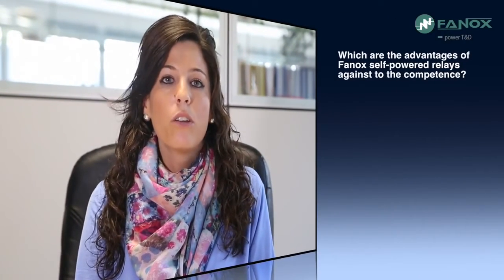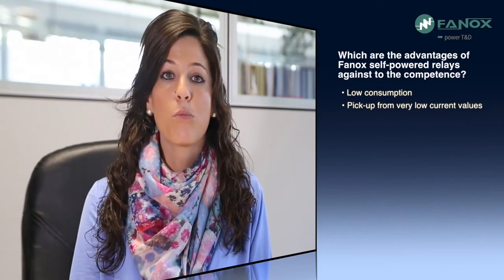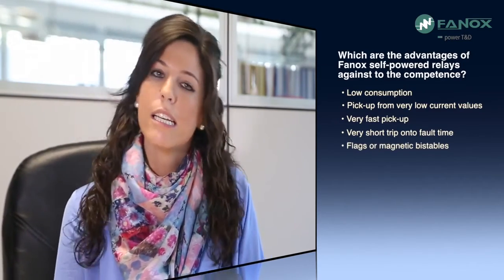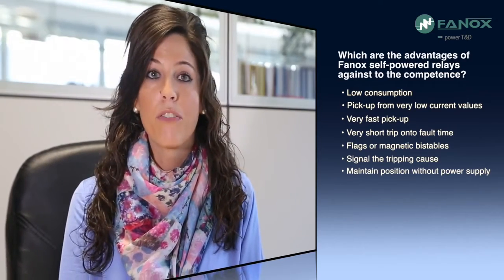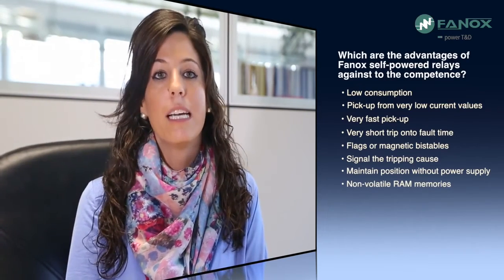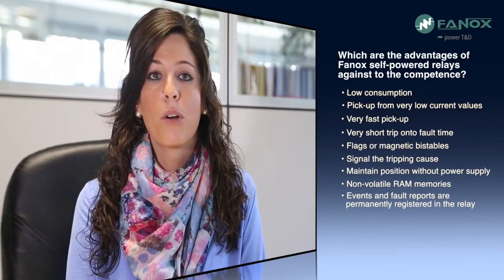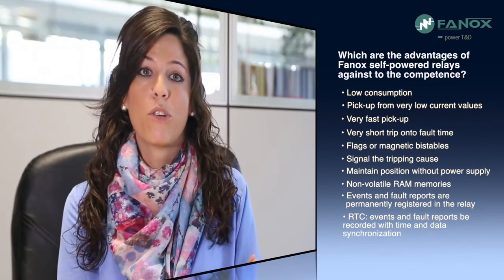What are the advantages of Fanox self-powered relays against the competition? Firstly, their low consumption and pick-up from very low current values, plus very fast pick-up allowing a very short trip onto fault time. All self-powered relays have flags or magnetic bistables — these elements change position when a fault occurs and maintain their position even without power supply, making fault detection practically instantaneous. Fanox self-powered relays also have non-volatile RAM memories, meaning all events and fault reports recorded during relay operation are permanently registered. Combined with real-time clocks, events and fault reports are recorded with time and date synchronization.